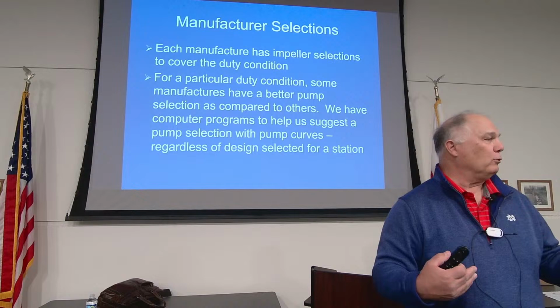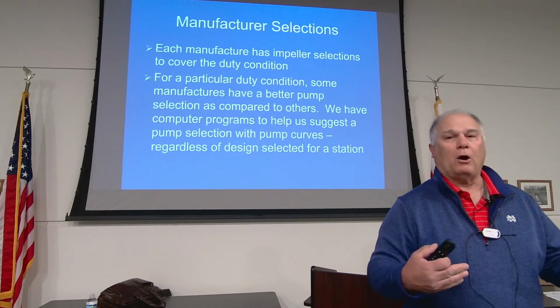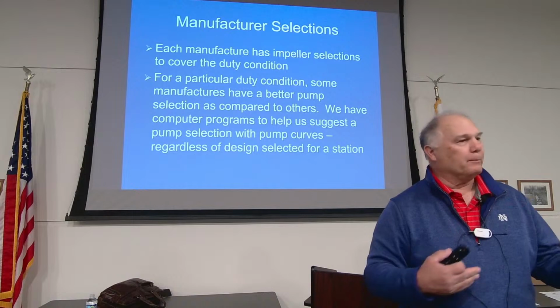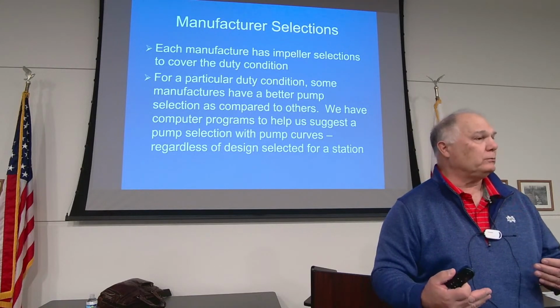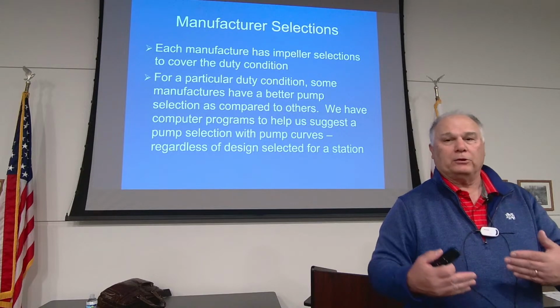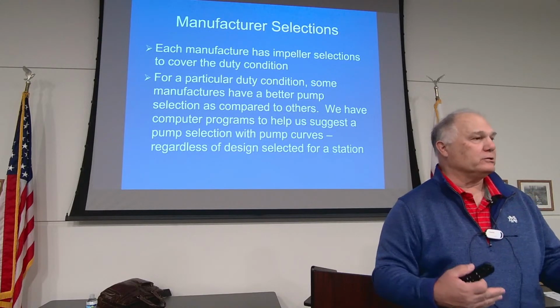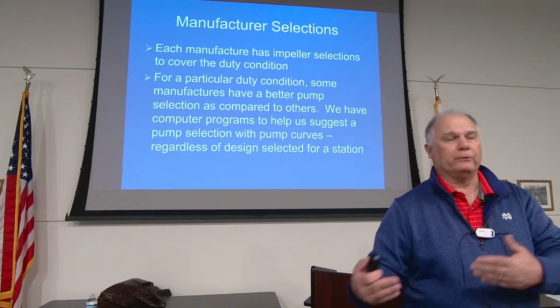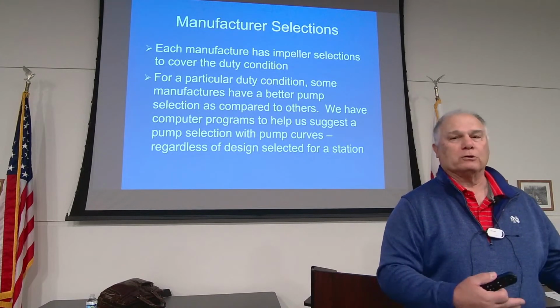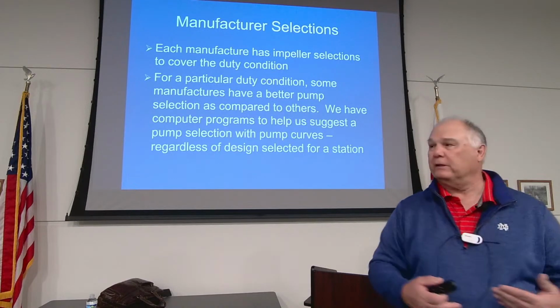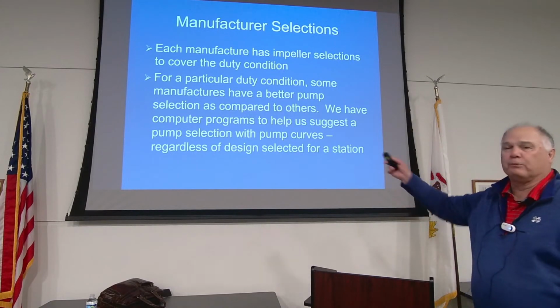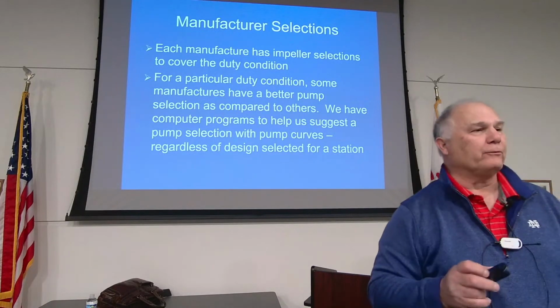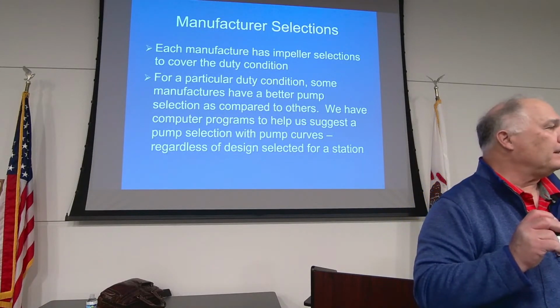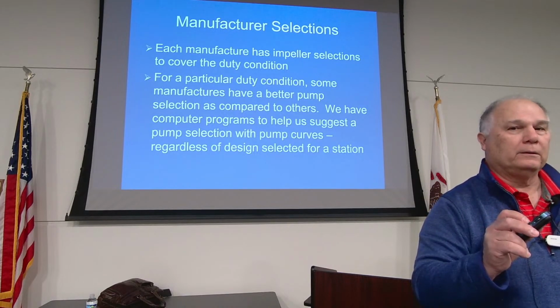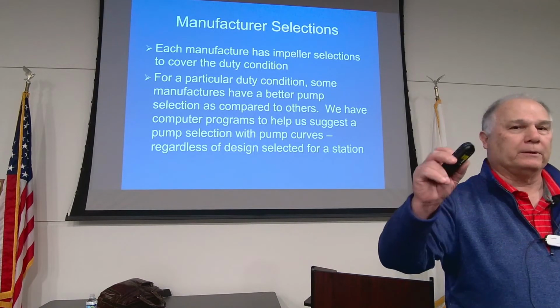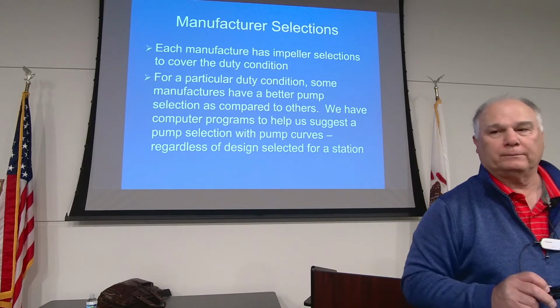But once you get below 20 horsepower, you can incorporate almost everybody into that business. The pricing is becoming much more of an issue, as well as you don't have to have such a big investment into that station. We're not talking about a 1,000 or 500 or 300 horsepower pump. It's a 20 horsepower pump. You can swap that out pretty simply. And we all have different programs that we can use. In the different programs that we use, you don't necessarily have to pick the most efficient pump, which is where typically most programs will go to.